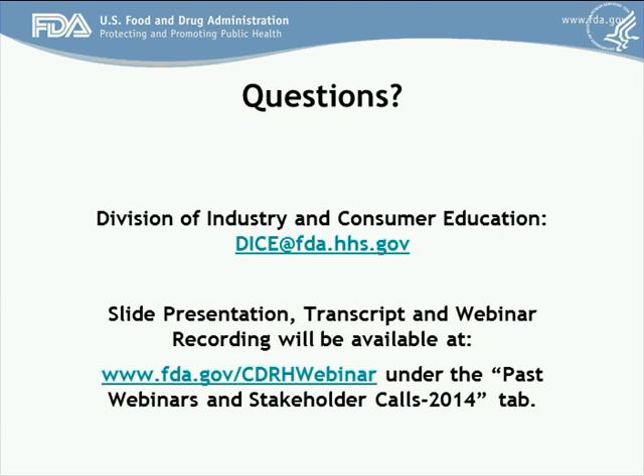So if it's a standalone unit and it's not hooked up to the internet, but there is perhaps a USB port in your system, so you can do physical updates to your system. Yeah, that's a potential vulnerability where the device, the patient data, or the functionality of the device can be compromised. So as part of your design of your device, that's a risk you should consider and mitigate for. Okay. So if someone inserts just any type of USB drive, maybe you can prohibit it, or it has to have a certain passcode on the USB drive. Again, the idea of this guidance is not to be prescriptive as to the method. It's just one of the areas of risk that we would like you to consider. Okay. All right, thank you.